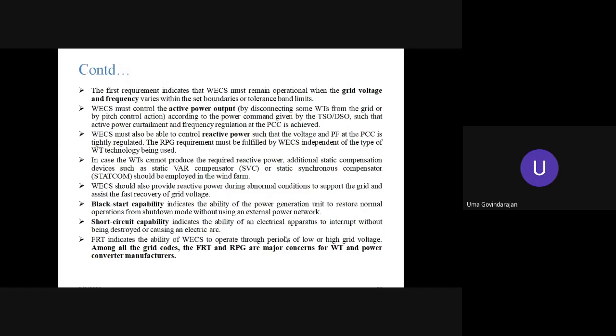Second, WECS must control the active power output according to the power command by the transmission system operator or distribution system operator, such that active power curtailment and frequency regulation at the point of common coupling is achieved. So, depending upon the TSO command and the DSO command, it is possible to disconnect a few of the turbines to ensure power quality. The WECS must have the capability to control the active power output. That is, by disconnecting some of the wind turbines from the grid, or by pitch control action, you can orient the direction of the turbine in another way where power generation will get limited, or minimized.